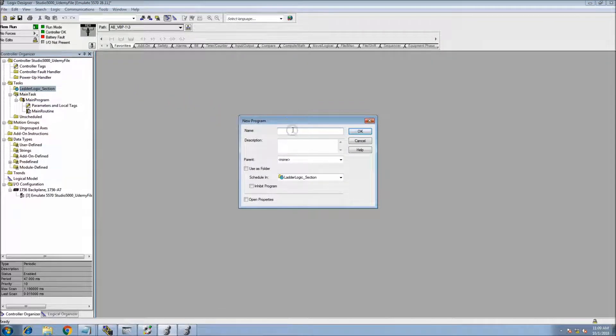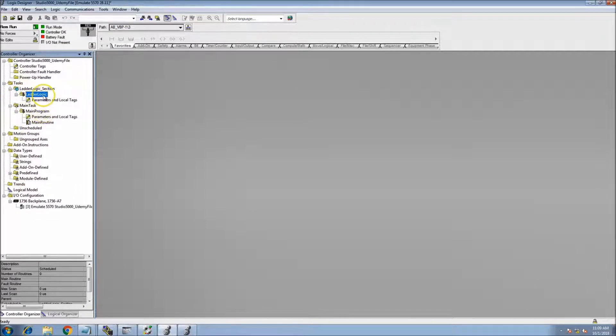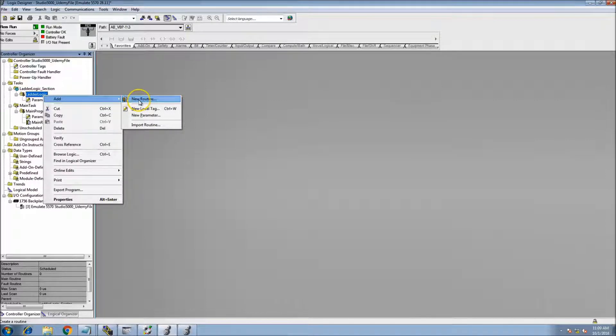We'll call the program 'Ladder Logic' and add a main routine. What we've done so far is add a task and change it to a periodic task. You generally want a periodic task so you understand timing better. You can use a continuous task if you like, but I'm a big fan of periodic tasks. If you're doing motion, you need to be in a periodic task.